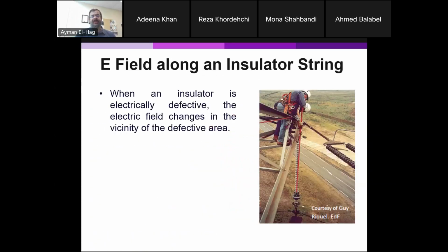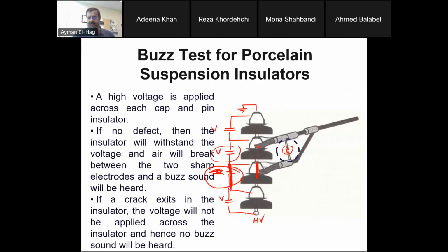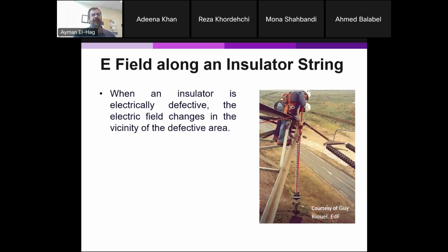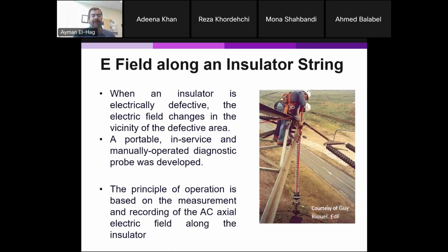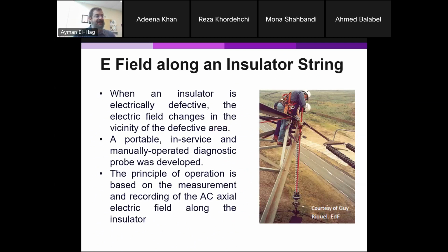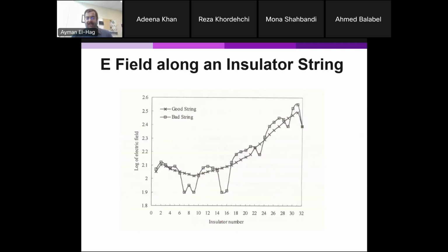Okay, so here you measure the electric field along the insulator string. Why that? Again, the insulator is energized. So you measure the voltage starting from the high voltage, and using the stick, you measure the voltage until the end. And then you draw the voltage versus the insulator number. Here we have 32. So you draw the electric field versus the number of the insulator in the string.